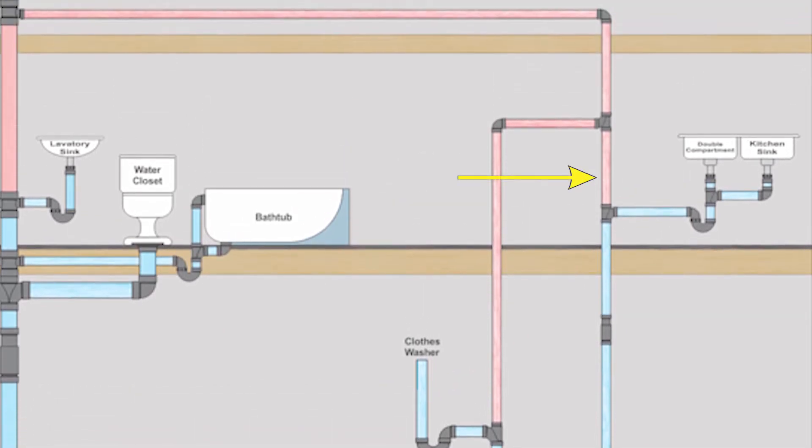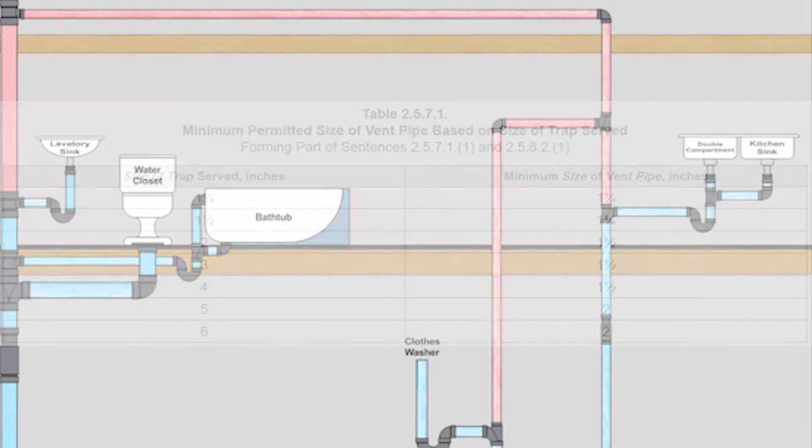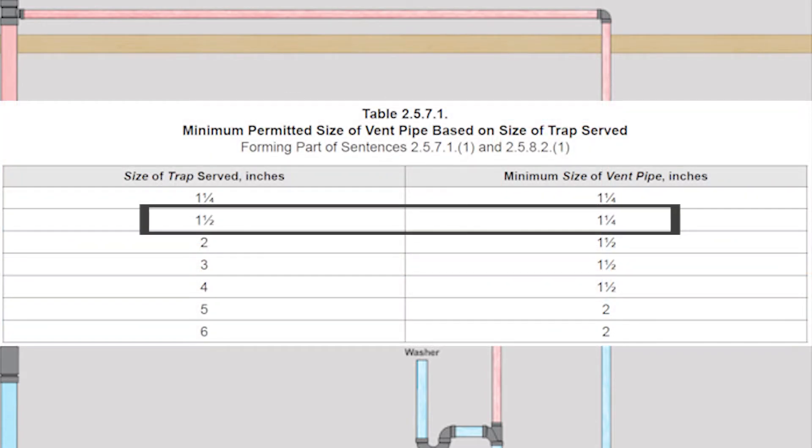Now let's look at this little vent pipe coming off the top of the soil-or-waste stack from the kitchen sink. Now that is called a stack vent. And we're gonna use table 2.5.7.1. We have a one and a half inch trap on the kitchen sink. Therefore we need a one and a quarter inch vent pipe.